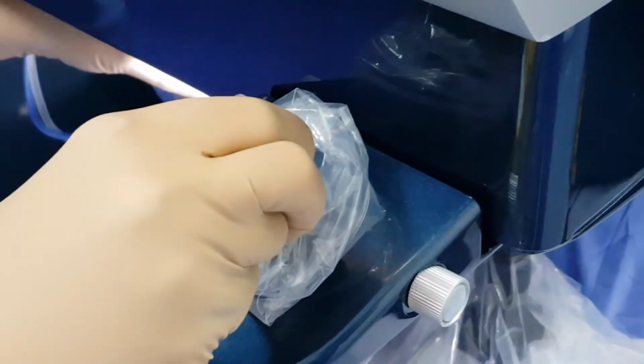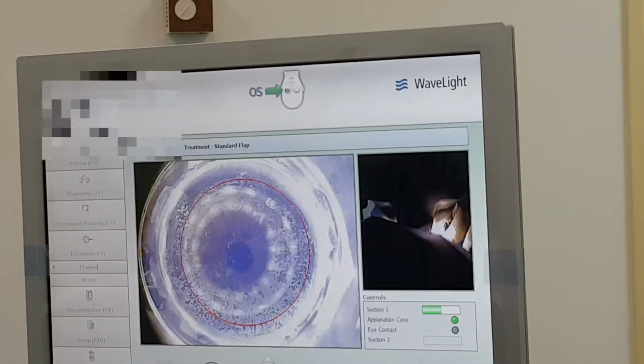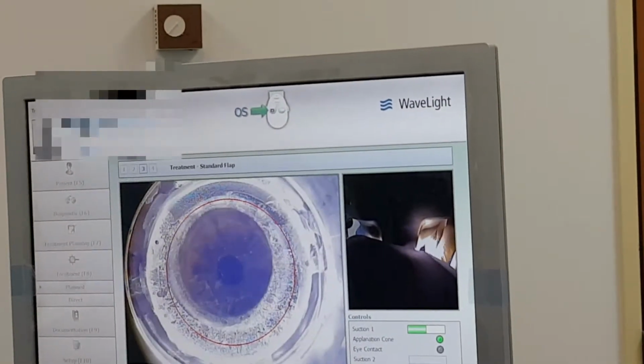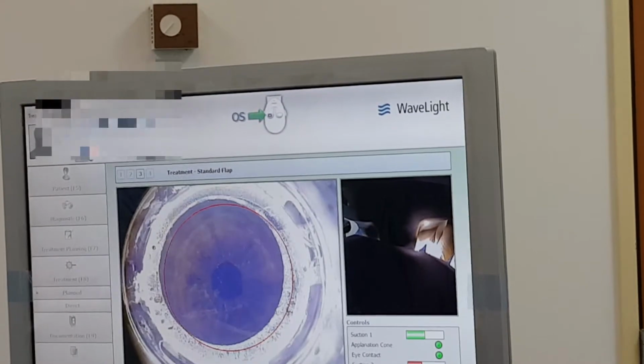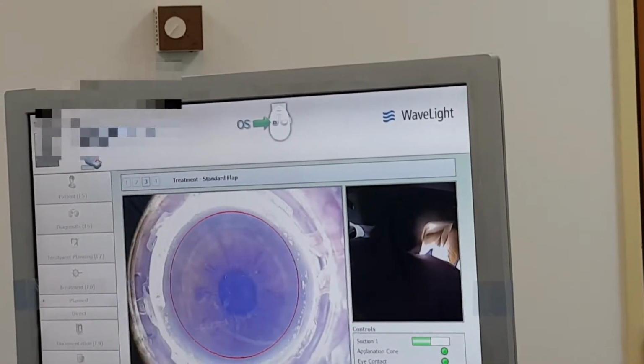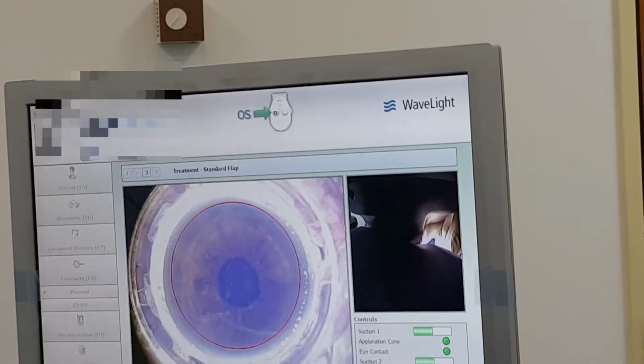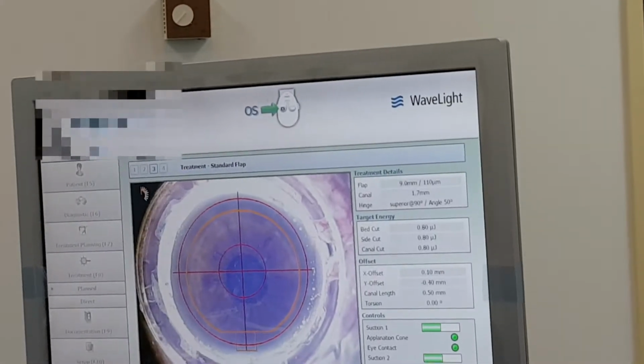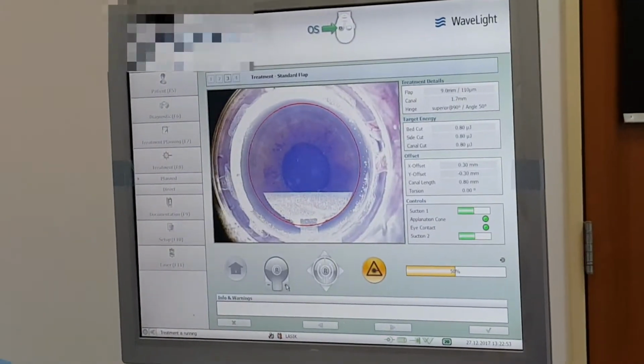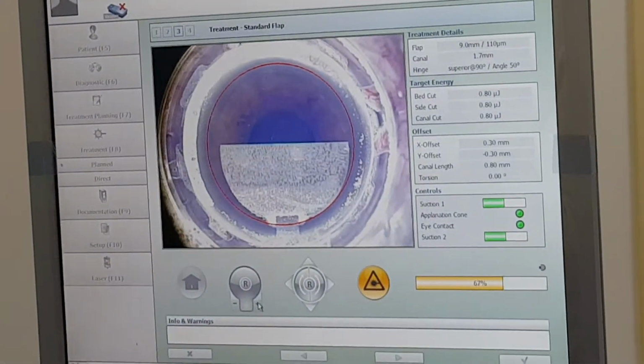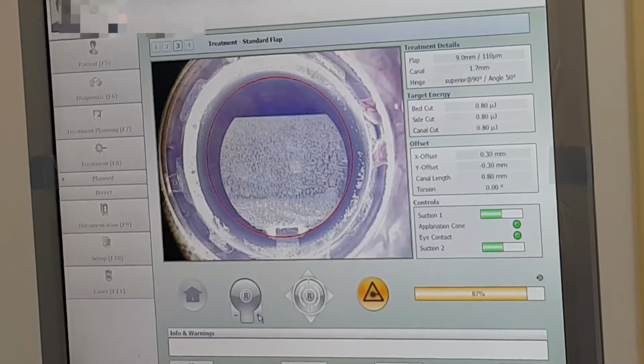Use the superior joystick to nest applanation cone into the suction ring. When applanation cone is properly seated, a pressure sensor will automatically stop the down motion of the applanation cone. Adjust the flap as needed, then fire laser, which usually takes 6 seconds to create the flap.